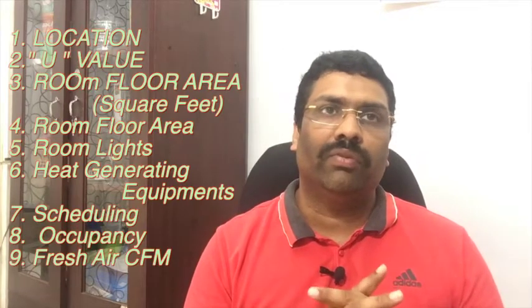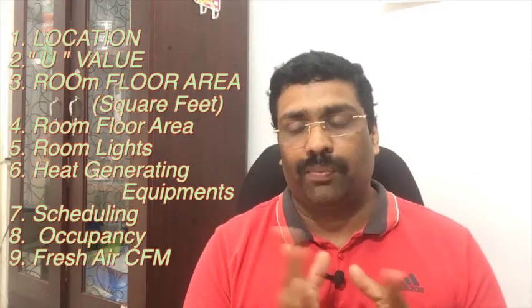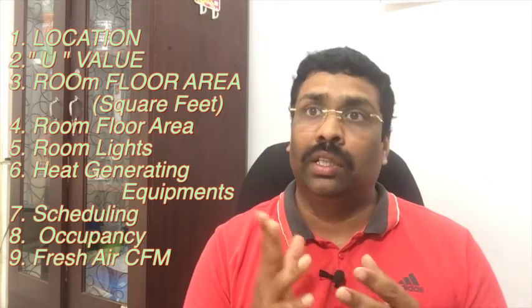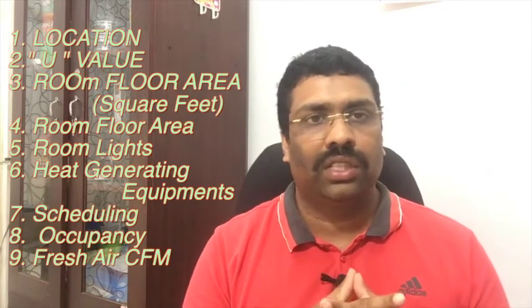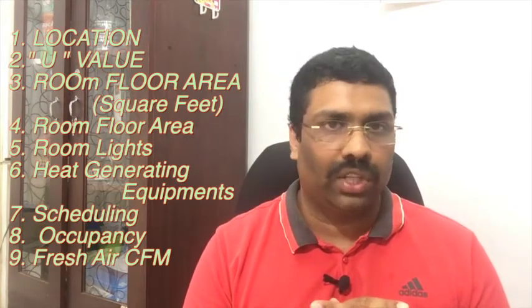And the 9th point is fresh air CFM. We need to consider fresh air CFM for a ducted split unit, if there is a fresh air unit connected to it. Normally for a wall split unit, fresh air is not there, so we don't need to consider that. In the old window AC, fresh air was coming. And in a centralized AC system like a chilled water system, of course, we take 10% or 8% fresh air from outside the building.